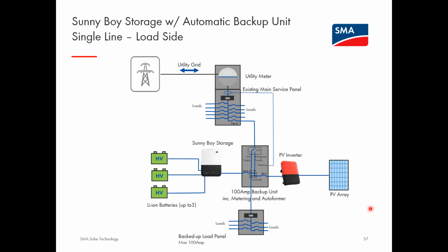In the event that they are co-located, and this is quite common for homes on the West Coast, California, where you have an all-in-one utility meter main service, generally what you would do is connect the automatic backup unit to a circuit breaker inside of the main service panel. You connect the input to typically a 100 amp breaker. And then you connect the output of the automatic backup unit to a backed up load panel, again typically somewhere like 50 or 100 amps.